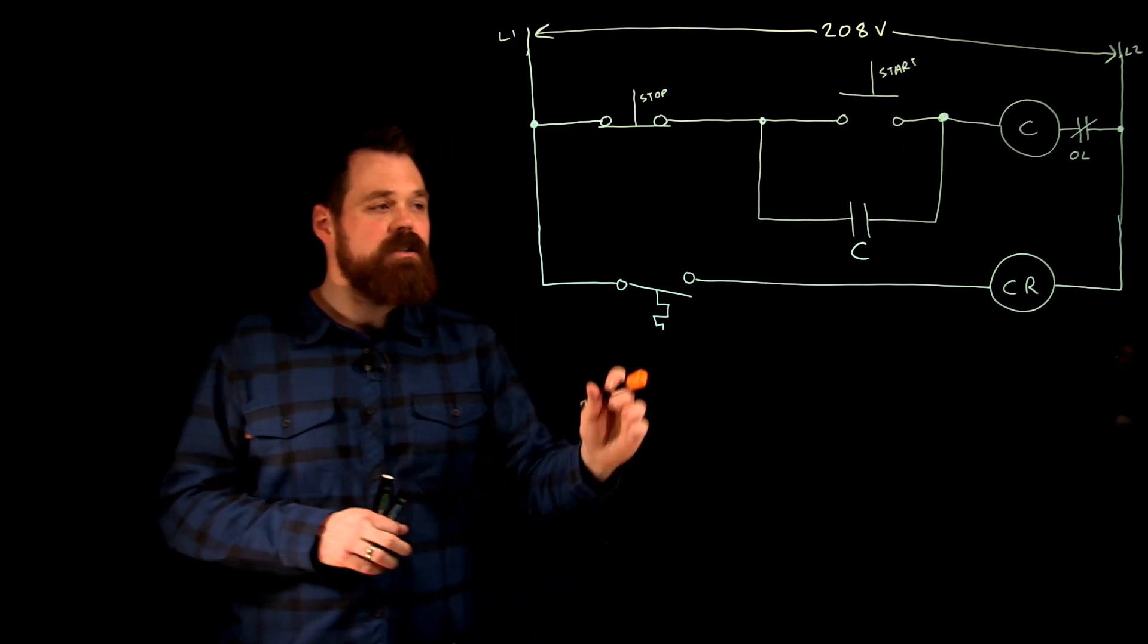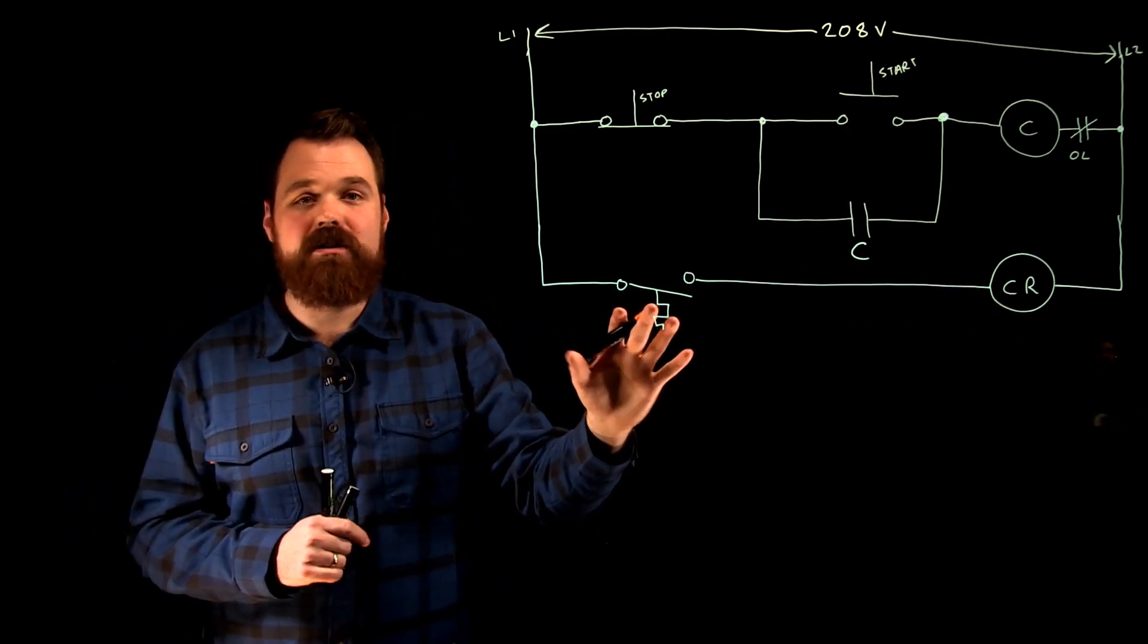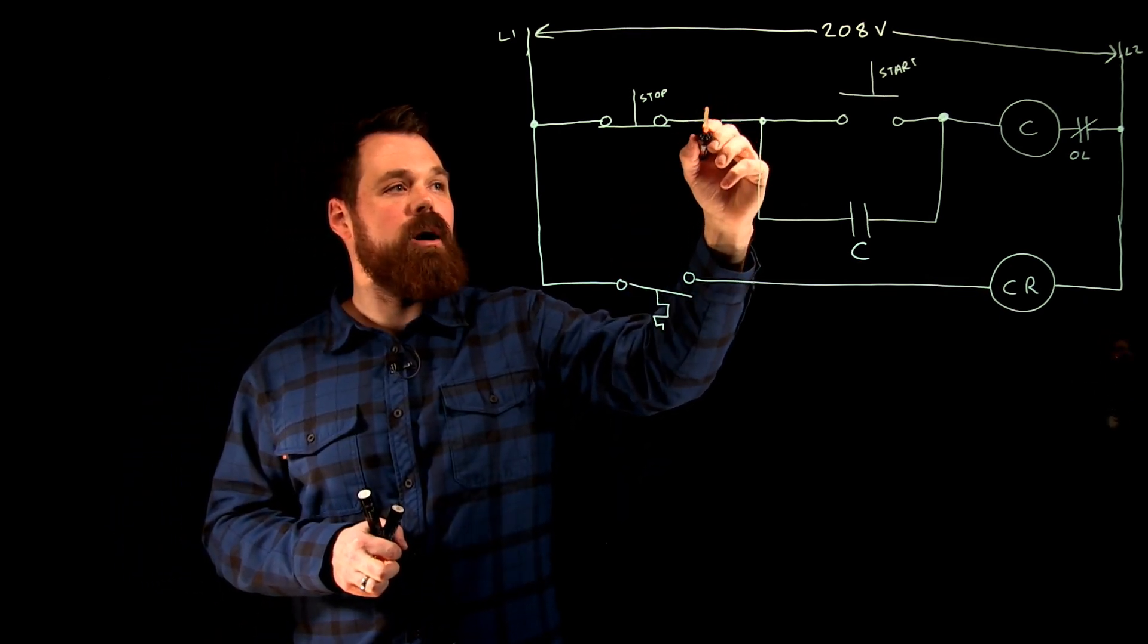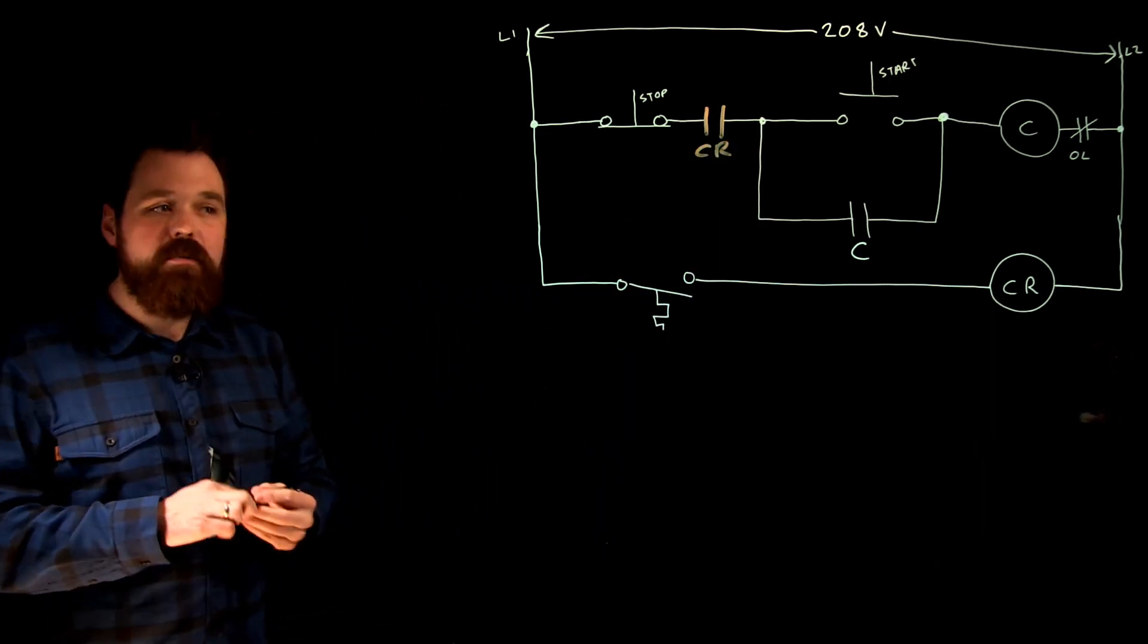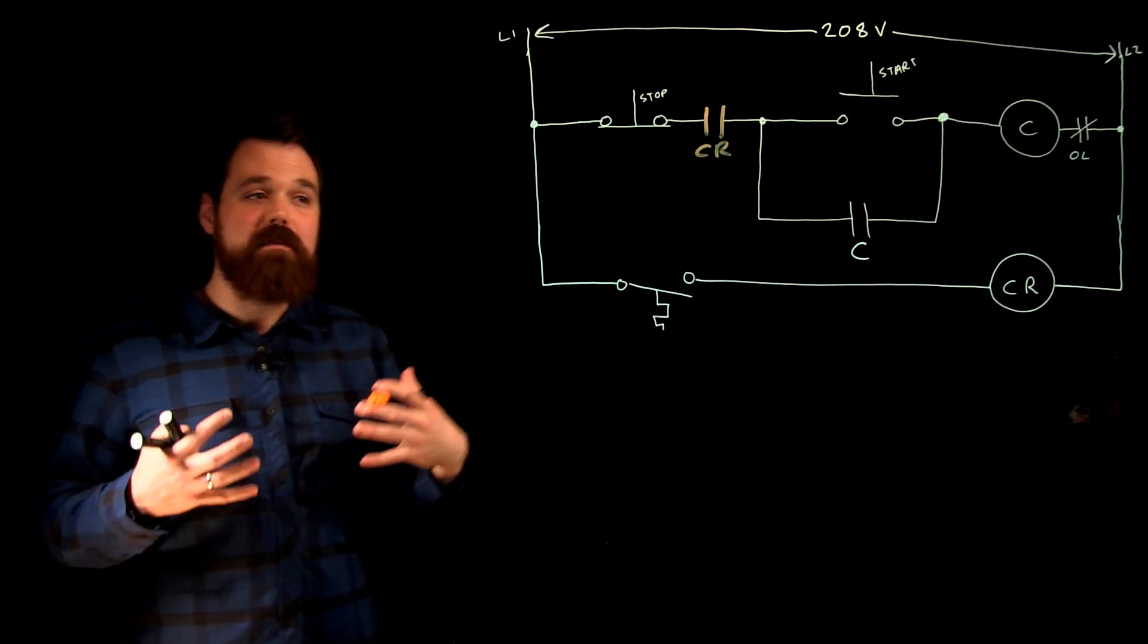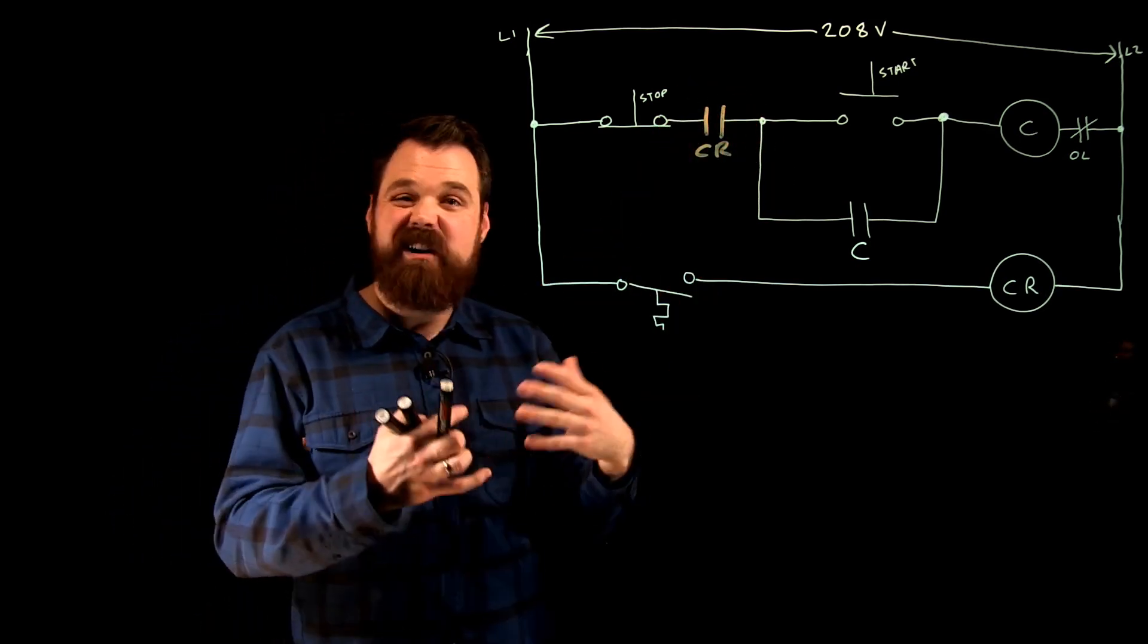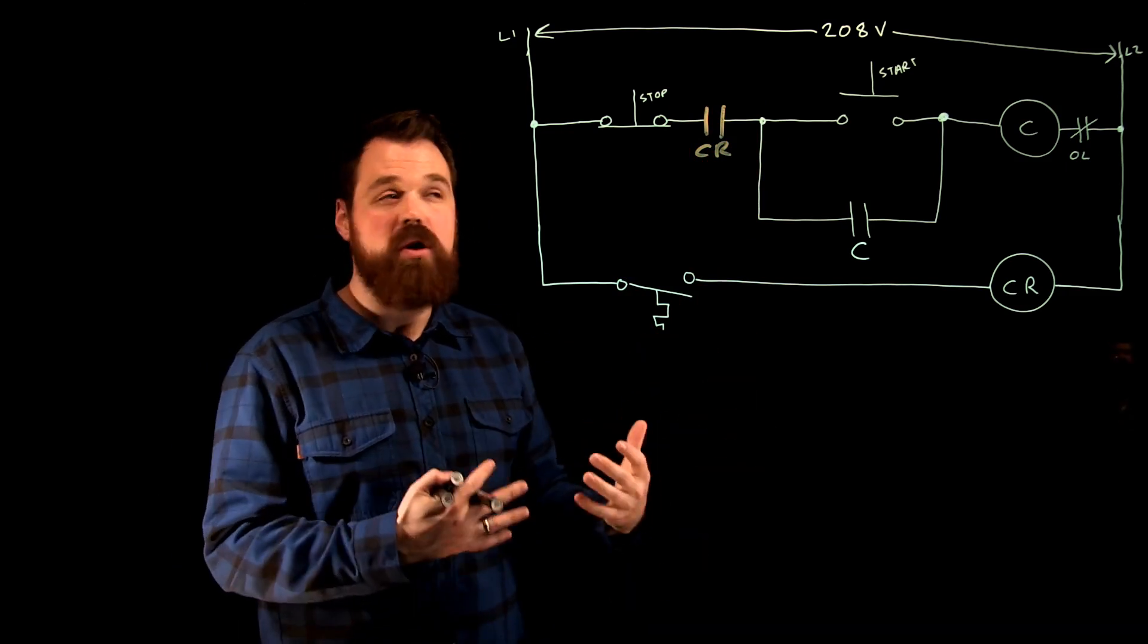So first of all, let's say I took a set of contacts controlled by CR which is controlled by this temperature sensing device, and I were to put it in my stop circuit. If I put that set of contacts in my stop circuit, when this set of contacts would be open, that would affect the stopping in that it would stop the motor. And it would also affect the starting of the motor. When this is open, I cannot start the motor.